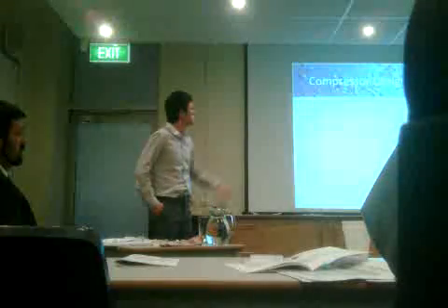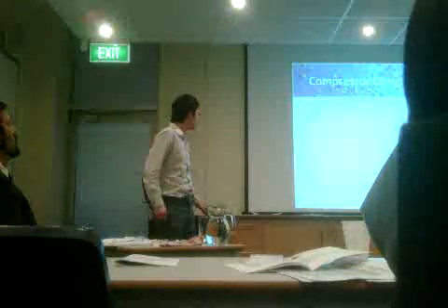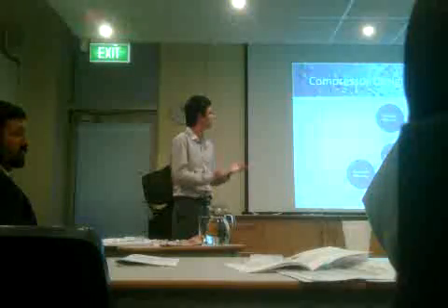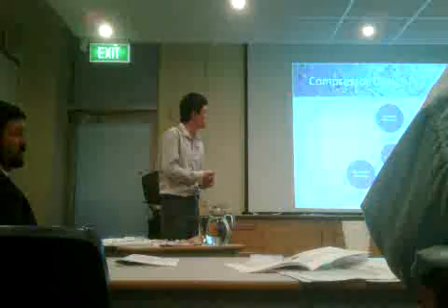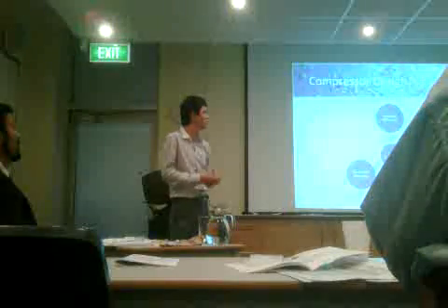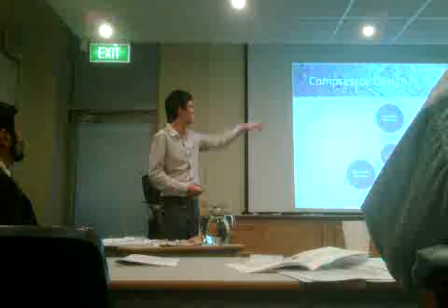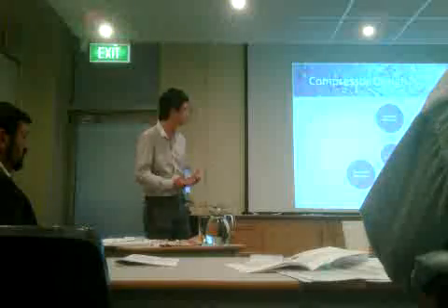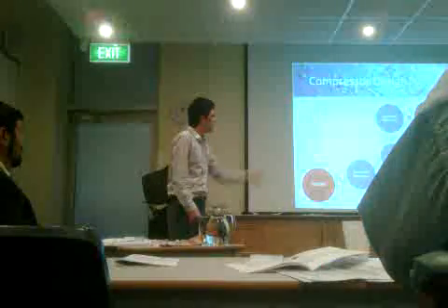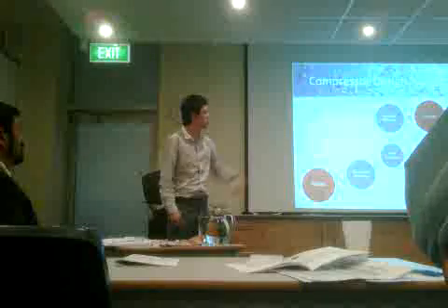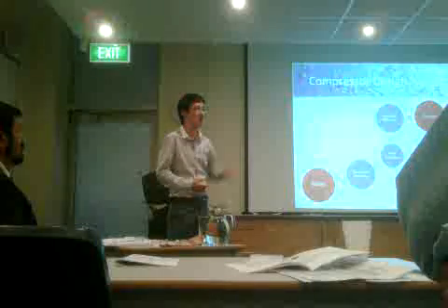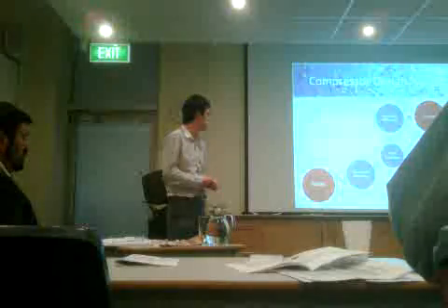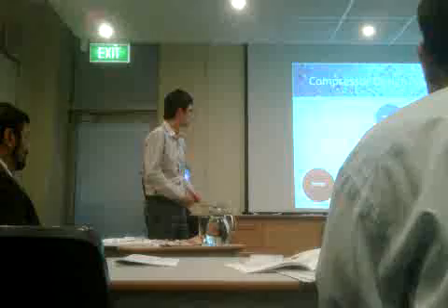The next important design is the compressor design. This figure here illustrates how we come about the compressor spec. The first important parameter we need to know is the inlet conditions. From this onwards, we can calculate the adiabatic efficiencies, compression ratios, as well as volumetric efficiency. And then finally, using these 3 important pieces of information, we can calculate the compressor power consumption, as well as the discharge temperature, and also the compressor speed.